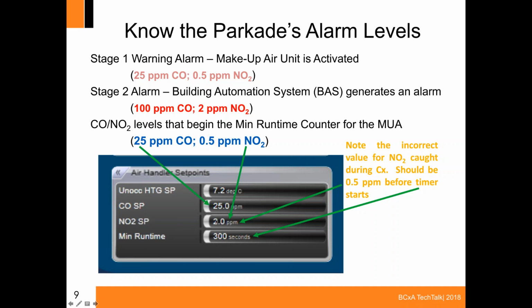For NO2, we would be looking at 0.5. You can see that on the snapshot, it actually says 2.0, which was an error caught during the commissioning process. At the stage 2 alarm, not only will your building automation system generate an alarm, but you will get a very loud audible alarm on the CO sensor or the NO2 sensor, which is very difficult to silence, which we found out while we were getting these snapshots. So this would occur at the 100 ppm for CO and 2 ppm for NO2, and then as they begin to drop, as I mentioned right in here, this is when our countdown timer starts, and you hope that by the time it shuts off that the gas levels are back down into the safe zones.